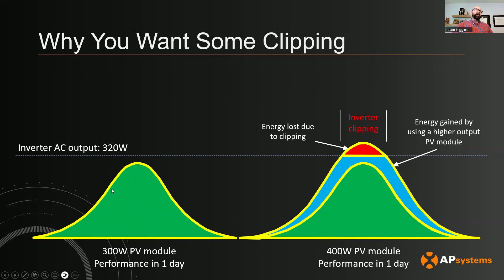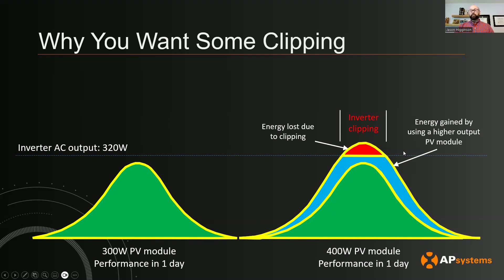Compare this 300 watt PV module with no clipping to the scenario where you have some clipping — but look at what you're also gaining on top of that green area, you're also gaining all of this blue. So in the end, you want to have some clipping. You want it to be appropriately oversized to account for STC versus PTC and for possible degradation over time. That's it — Clipping Explained. I'm Jason Higginson with AP Systems and we'll tackle more of your questions soon. Thanks.